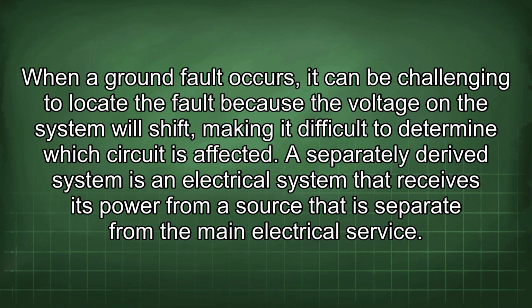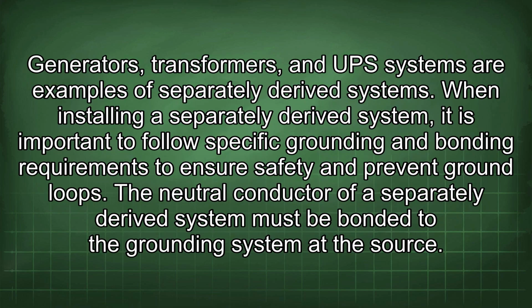A separately derived system is an electrical system that receives its power from a source that is separate from the main electrical service. Generators, transformers, and UPS systems are examples of separately derived systems. When installing a separately derived system, it is important to follow specific grounding and bonding requirements to ensure safety and prevent ground loops.